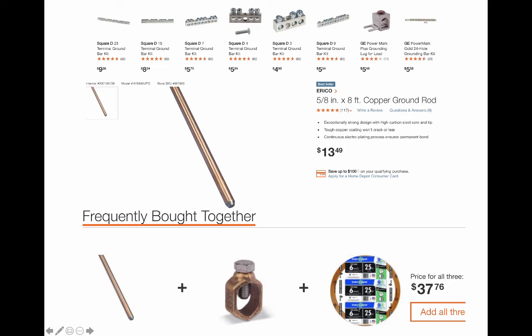And we have this wire that's 6 gauge bare copper wire, 25 feet of it. And we can go to the bus bar from that 6 gauge copper wire, or it could just be somewhere in your main service panel that might already have one of these things. But if you have a disconnect, you might have to add one of these things. It's just different depending on what type of system you're doing. Then you've got that number 6 copper, 25 feet of it. Hopefully that's long enough. And you are bringing that to this bolt right there, and you are bolting this onto that 5/8 inch diameter ground rod that's 8 feet long.